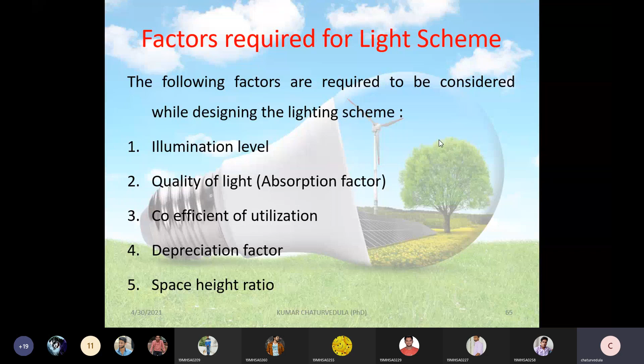Then what is illumination level? I told you it is the very vital factor which decides the number of wattages for a luminary. Okay, so lumen per watt. First of all, you should decide whether we are going to install it for office work. The recommended illumination level is 100 to 400 lumen per meter square. So in general, for 1 meter square, the recommended level is 100 to 400 in case of offices.